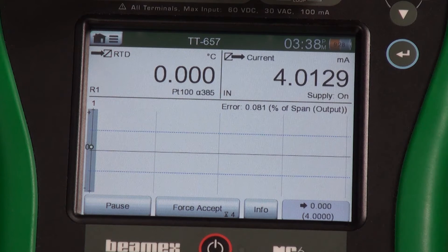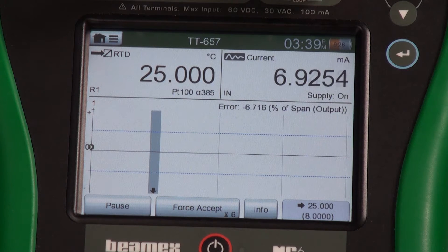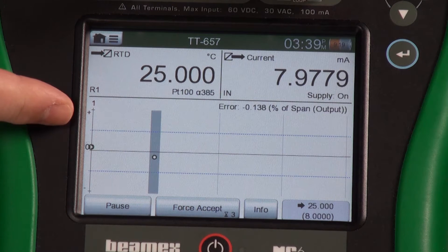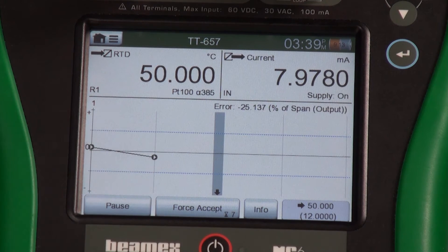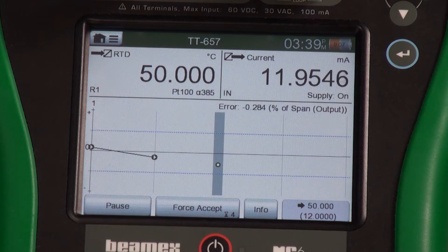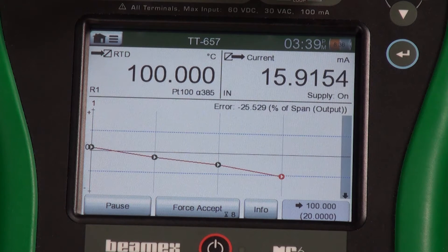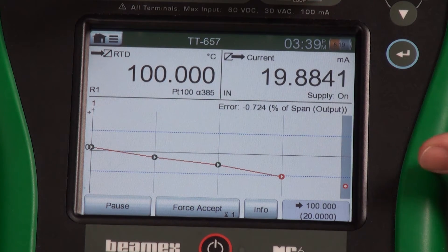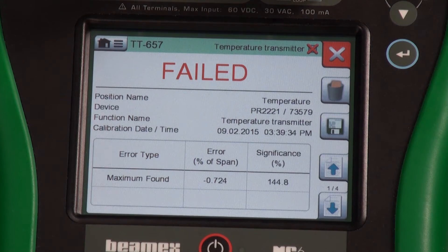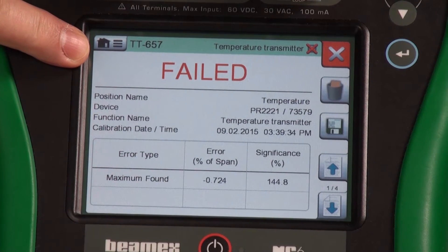The bottom right gives you an indication of where we're going — it tells you the next test point and the expected output current. We've got the first test point set, and we're on the second one now. I've got an eight-second delay on each test point just to allow for settling, in case you have a longer damping section inside the transmitter that takes a while to ramp up or down. Right now we're on our final 100-degree test point, and you can see that our final two points have turned red, which means they're beyond our passing section — past the blue lines — which means it actually fails.